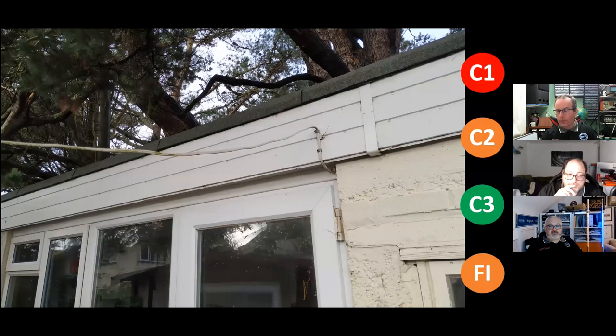And I would absolutely ban twin and earth being clipped outside a building without suitable UV and mechanical protection on it. Yeah, there's a couple of things. There's UV, obviously. Then we've got to think about things like the travel that conductors take under temperature. So if these conductors are going out and they're under little to no demand, then you're not going to see much unless they're constantly being under UV light. But if you're going to go to a shed that's got a washing machine or a tumble dryer, and you're going to constantly turn that on, then that changing of temperature could break down the insulation as well.